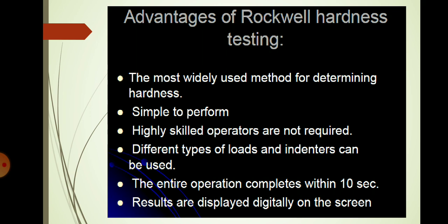Next advantage, the entire operation completes within 5 to 10 seconds, and you will find the final reading. The results are displayed digitally on the screen directly or through the pointer, so it is not necessary to do any other calculations. These are some advantages of Rockwell hardness testing.